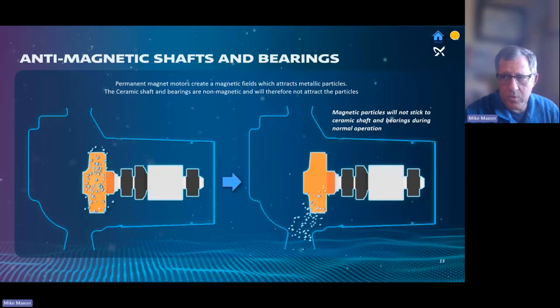It is a permanent magnet rotor. Being permanent magnet, a lot of people are afraid that it will attract metal particles to it, but the shaft and the impeller are not magnetic materials. They're ceramic and composite, so they will not attract these materials. And since there's a bearing plate here, they can't get into the rotor, so we're safe from those.